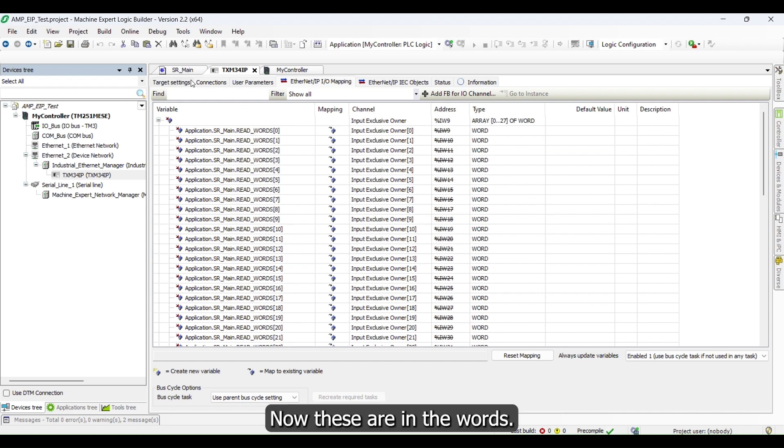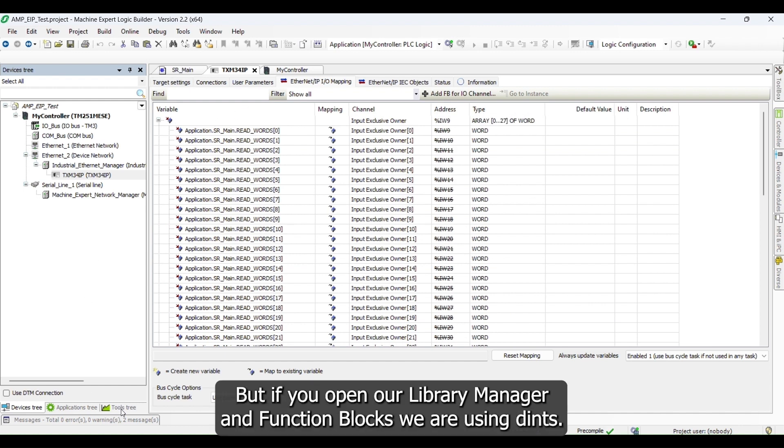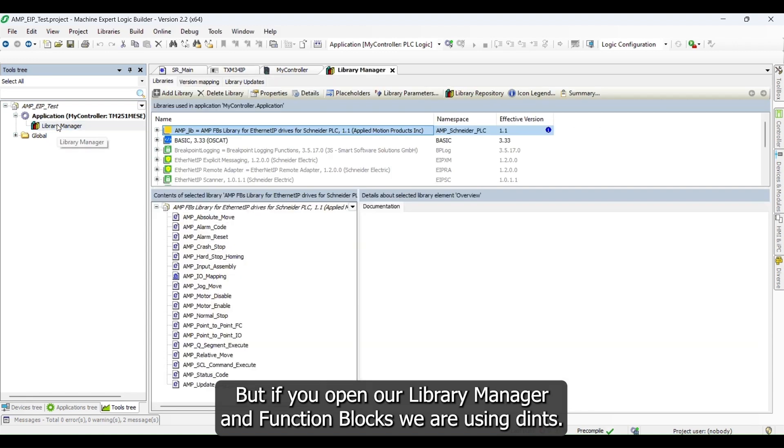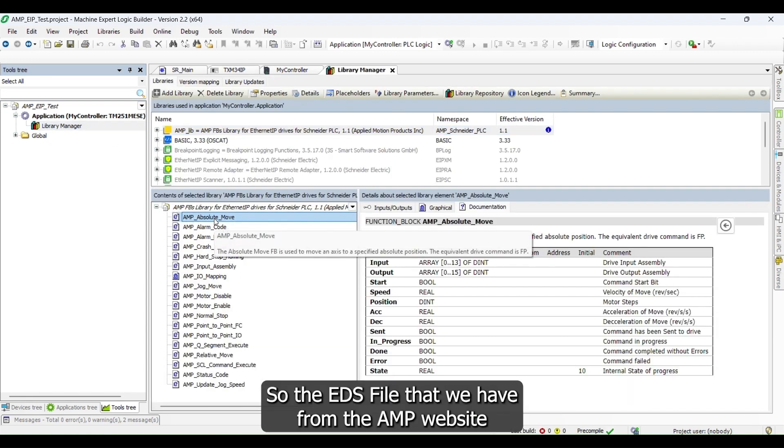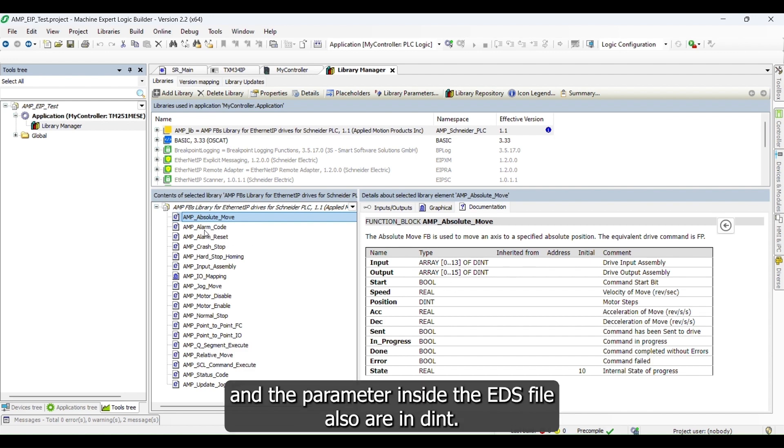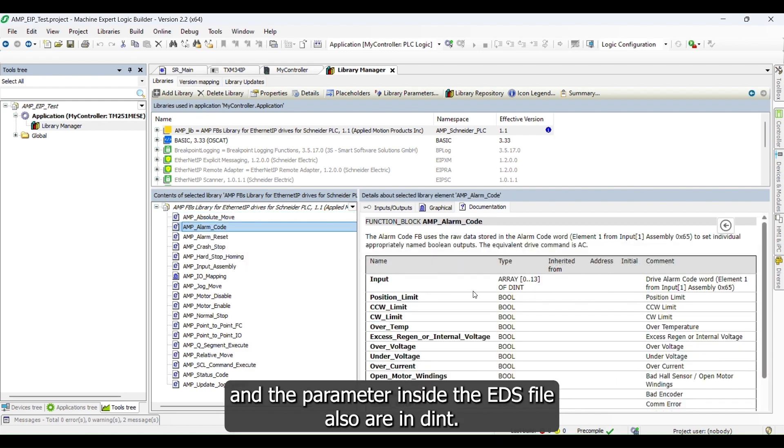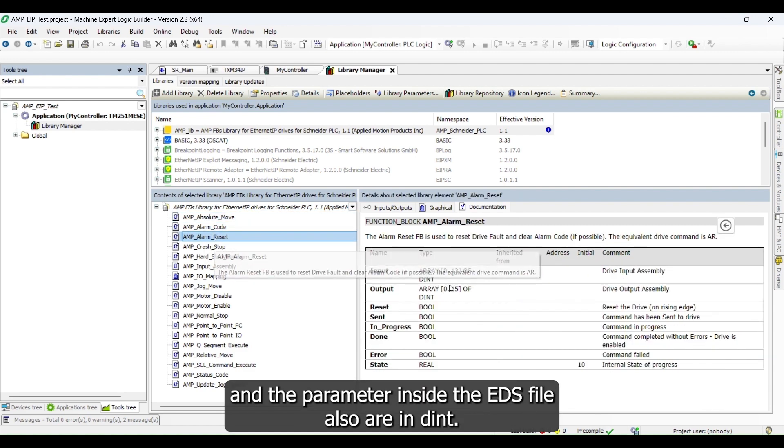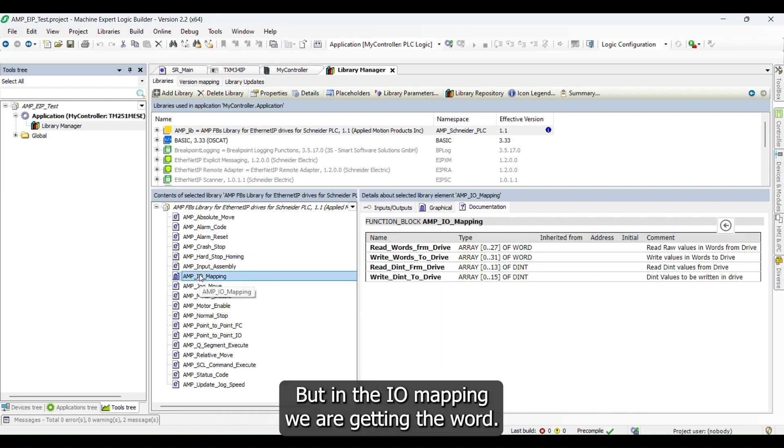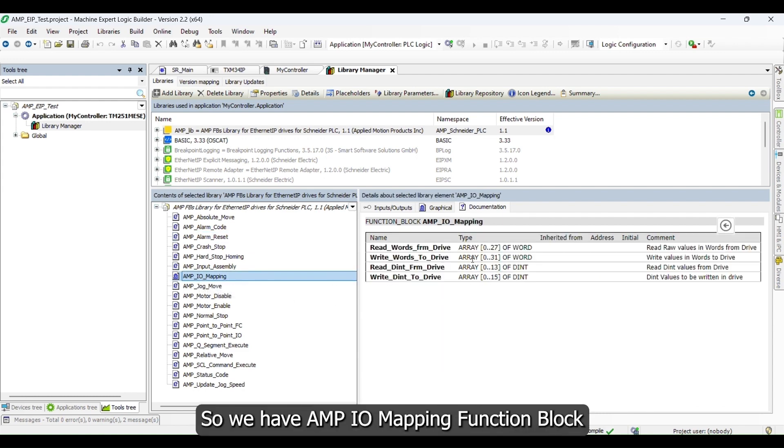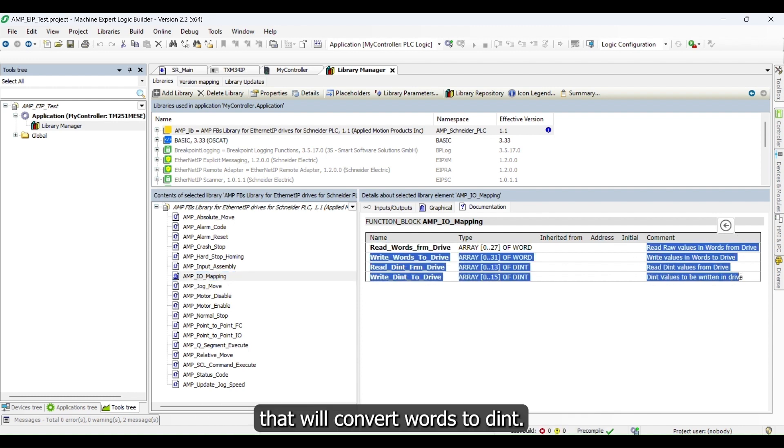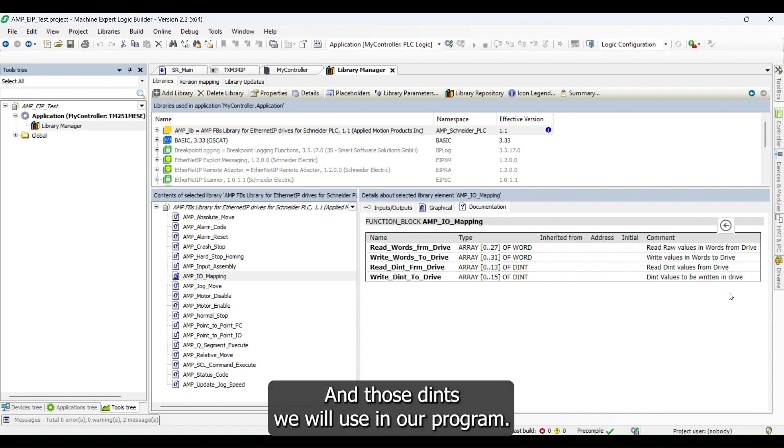Now these are in words, but if you open our library manager and function blocks, we are using DINT. The EDS file that we have from the AMP website, the parameters inside the EDS file are also in DINT, but in IO mapping we are getting word. So we have AMP IO mapping function block that will convert words to DINT, and those DINTs we will use in our program.